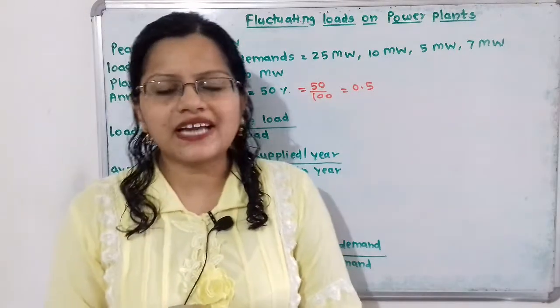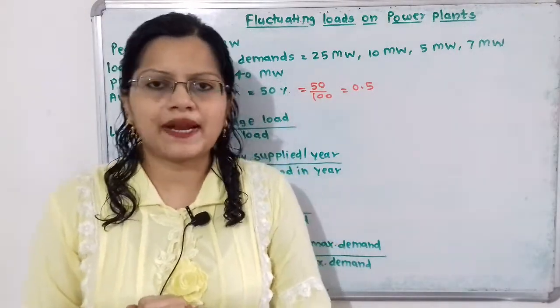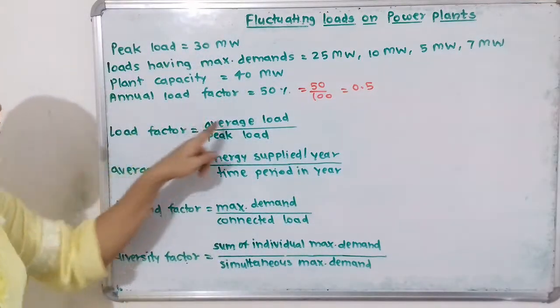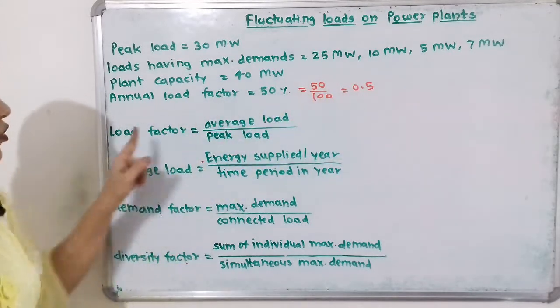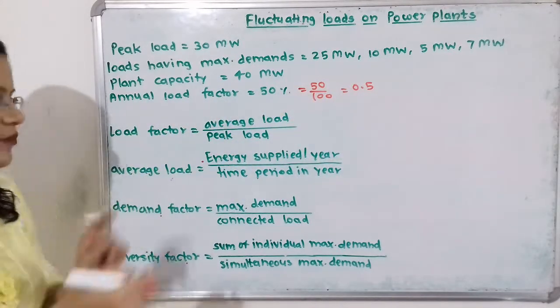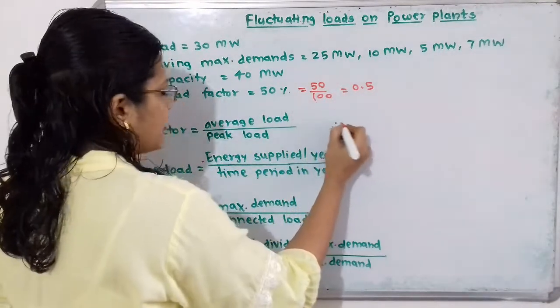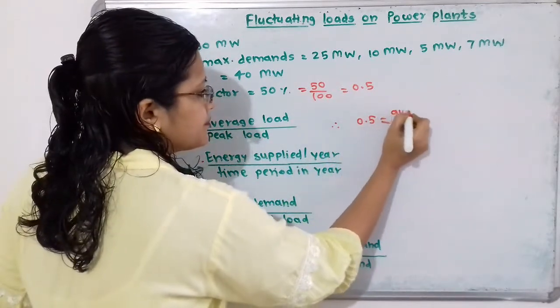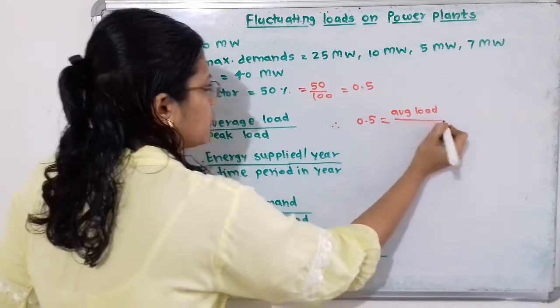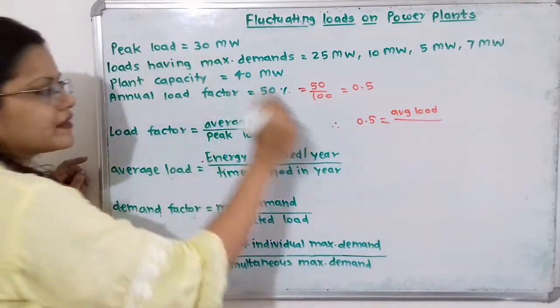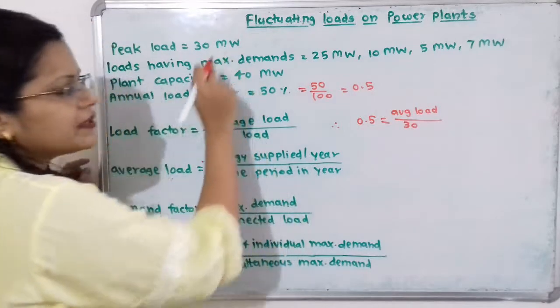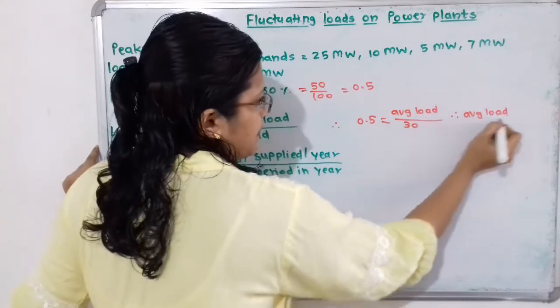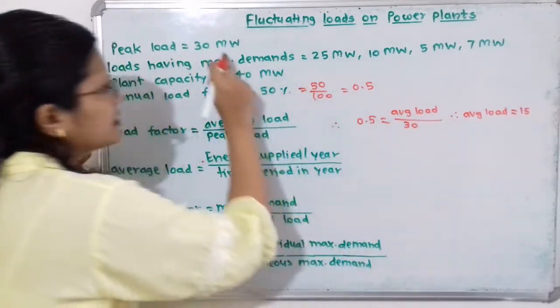Now we will move to the first calculation: average load. Load factor is given, and load factor equals average load divided by peak load. Therefore, 0.5 equals average load divided by peak load. Peak load is 30 MW, so average load equals 30 multiplied by 0.5, which is 15 MW.